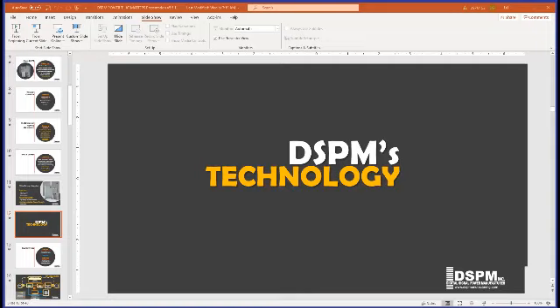Similar to the previous question, how is an inverter different from a UPS? At DSPM, we explain that a UPS typically includes the inverter, battery, and battery charger in one standalone unit. More importantly, UPSs typically have a communication link with the equipment it's powering, letting the device know it's operating on standby mode, giving it time to shut down or warn a human to do so. Inverters, however, typically don't have this communication and are designed to keep everything running as long as possible.